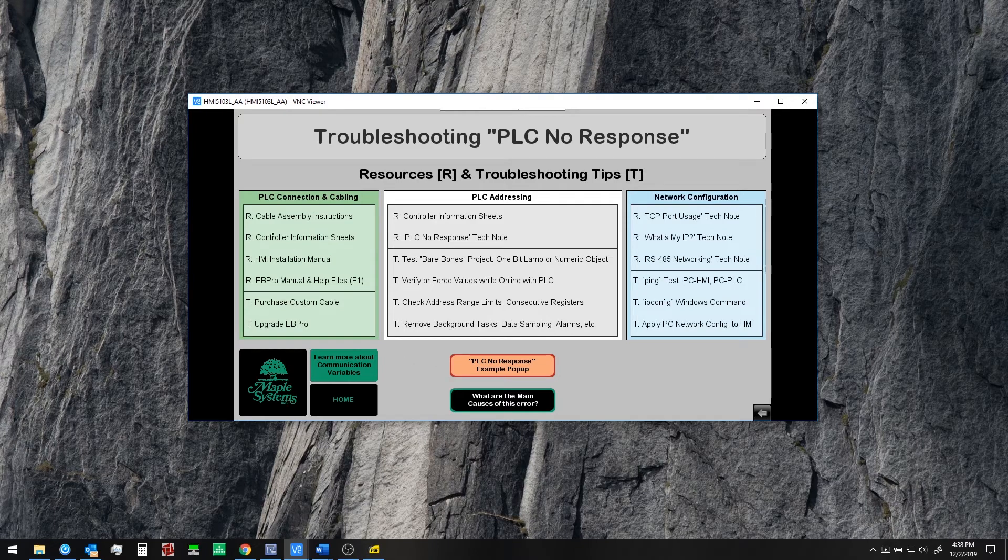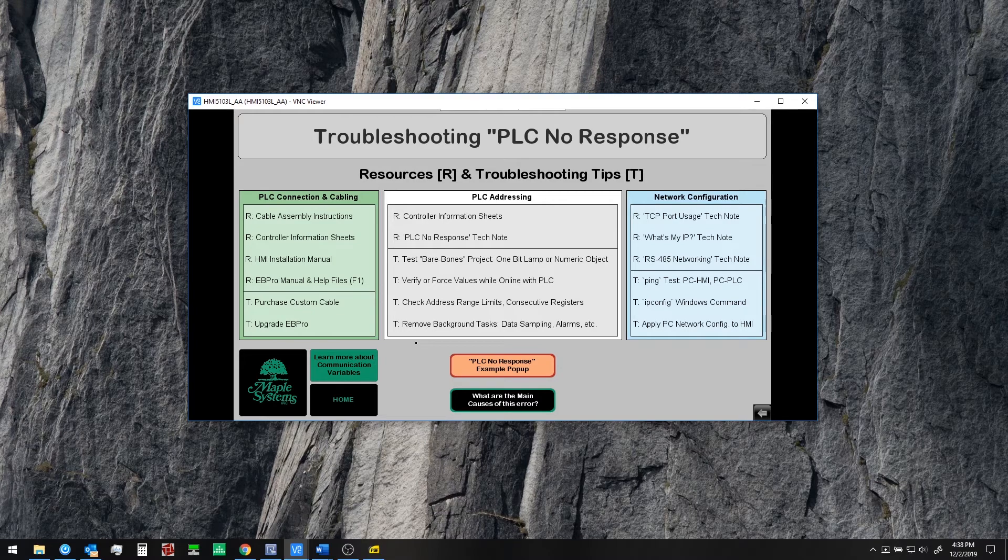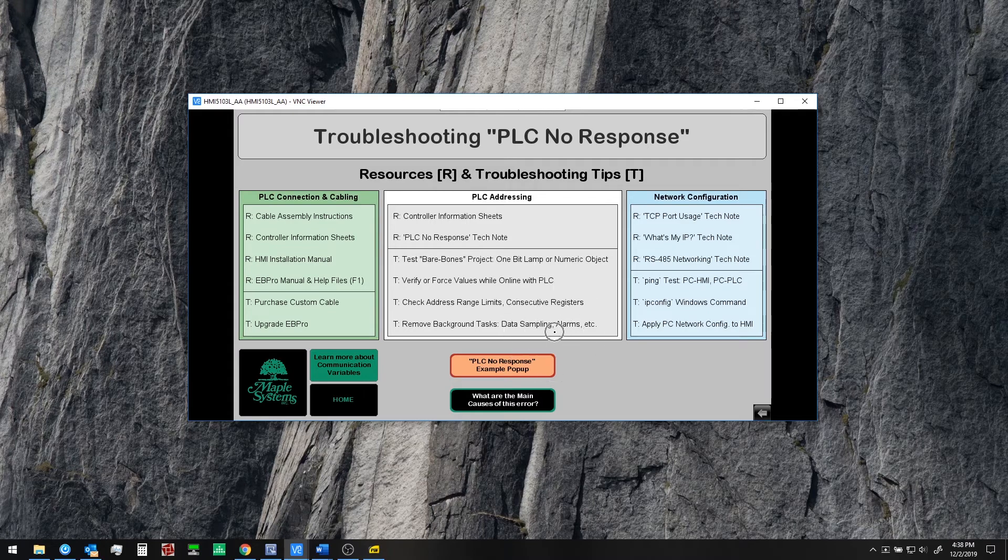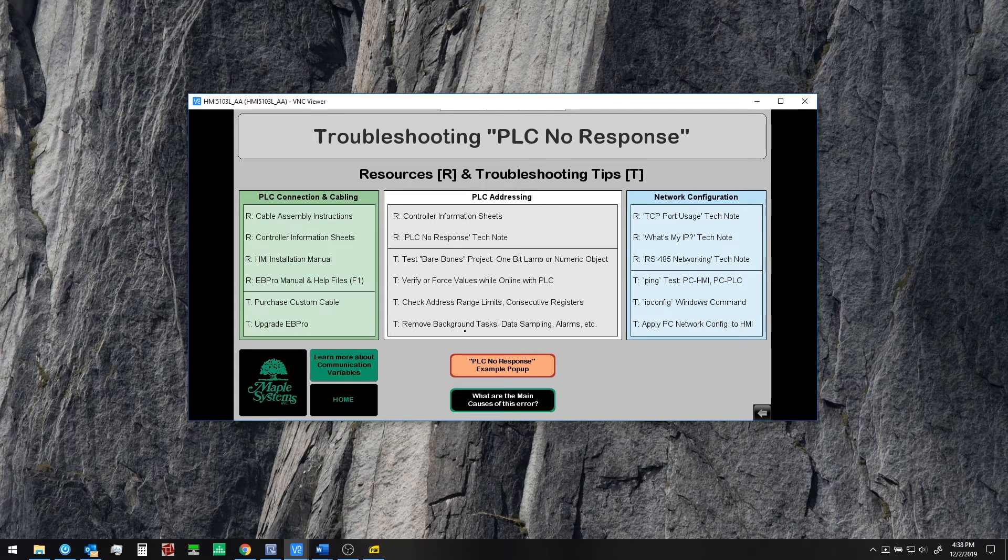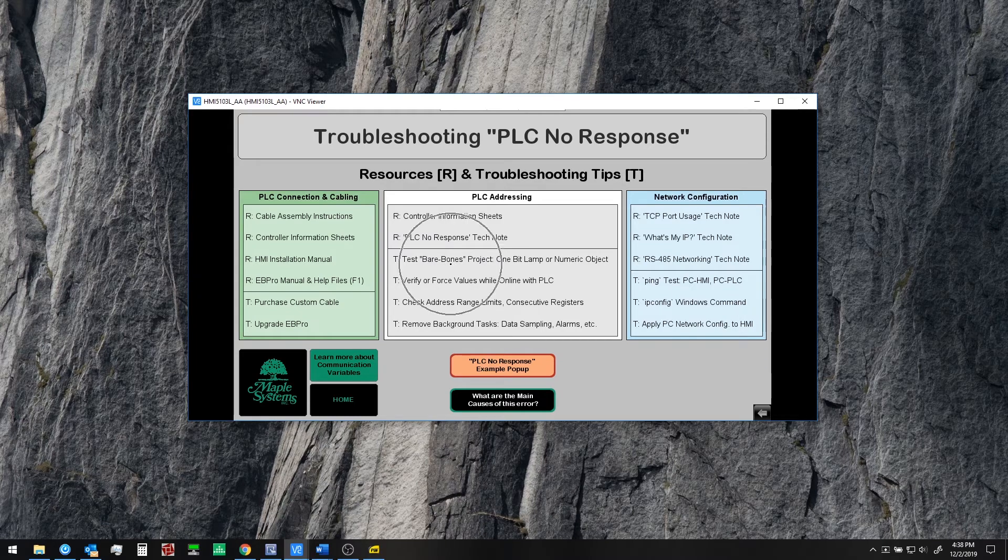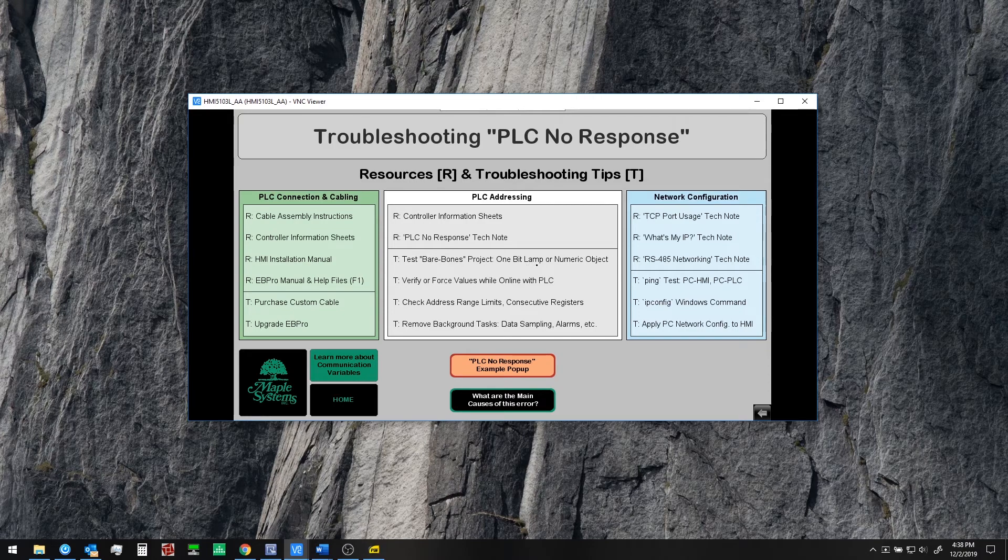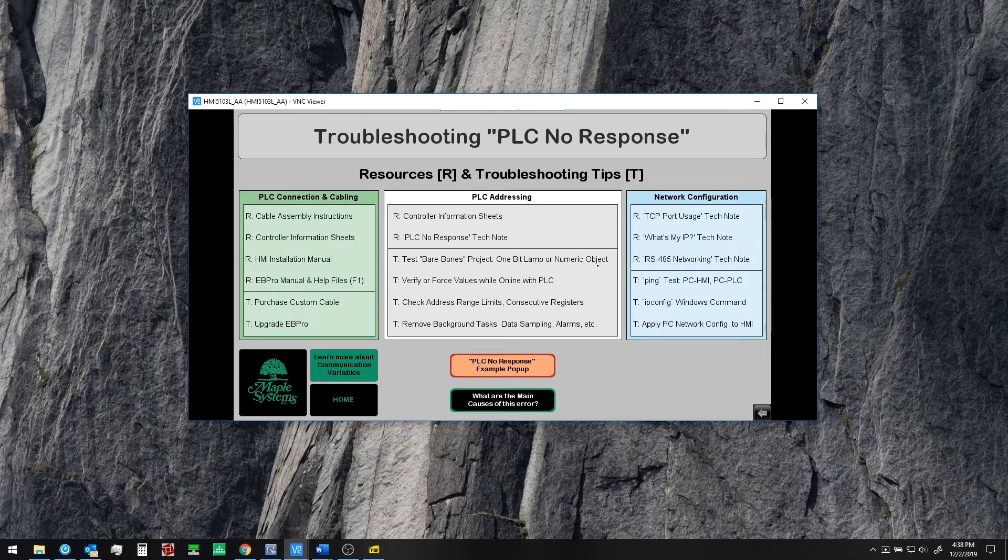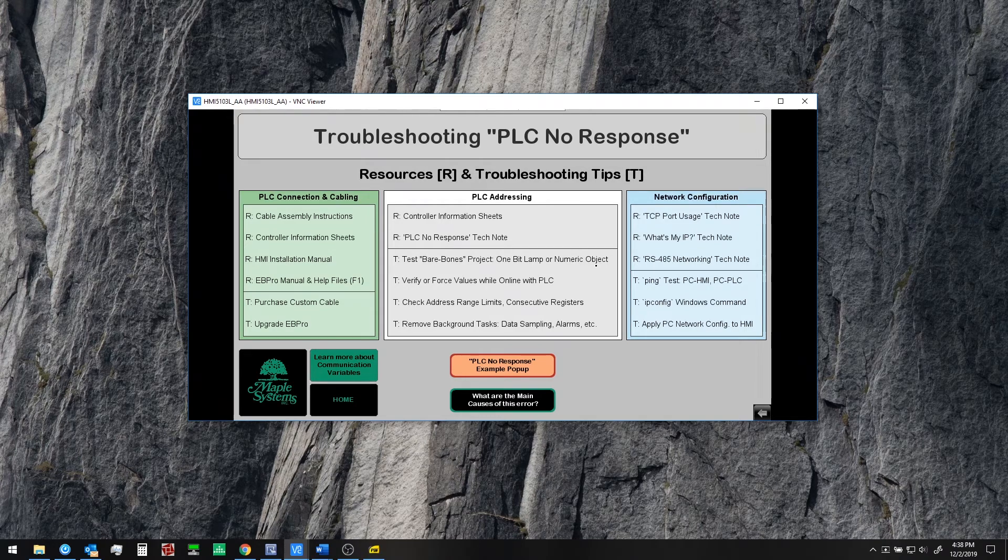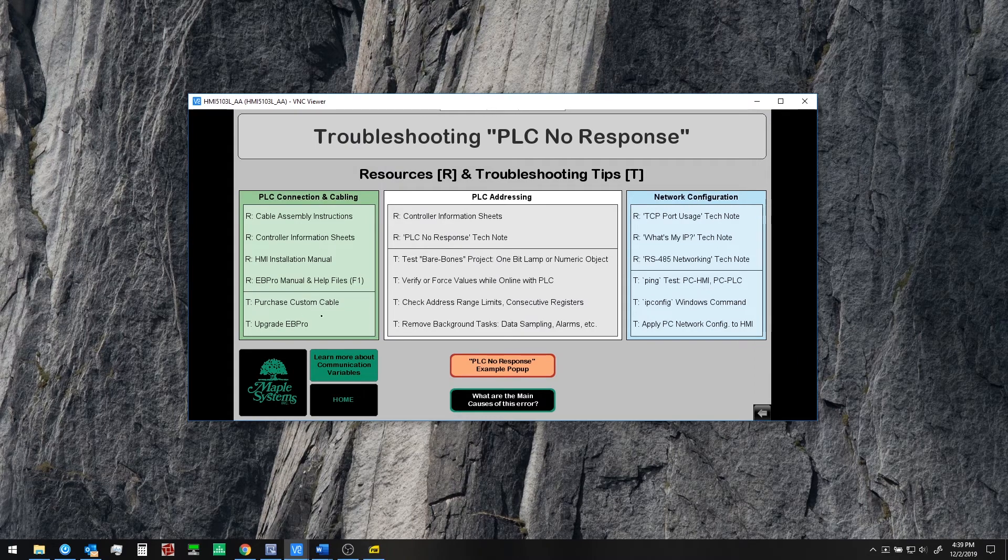So here we have resources marked with an R and tips marked with a T. So as we discussed you may want to remove background tasks if they are pointing at invalid registers or potentially doing so. And sometimes it's just simpler to create a test project a bare bones project with a single bit lamp or numeric object on the screen pointing at one valid PLC register. That can often clear it up whether it's actually an addressing issue or whether it's a protocol or communication settings issue or a networking issue.